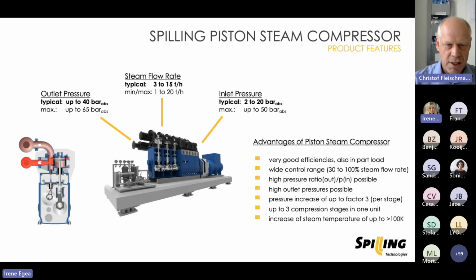So a 3-stage compressor could look like this, that at the inlet, at the first 3 cylinders, for example, we have 2 bar being compressed to 6 bar steam. Then the steam is going to the next 2 cylinders where it's compressed then from 6 to 15 bar. In the last high pressure cylinder, it's then compressed from 15 to 25 bar. And this all in one machine. And by this, the saturated steam temperature can be increased for more than 100 kelvins.